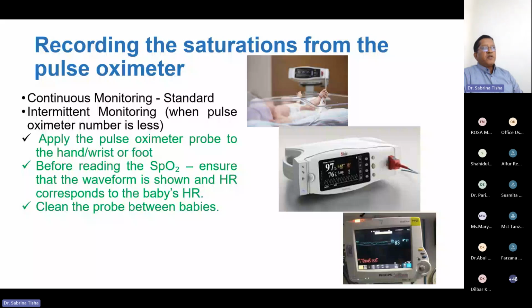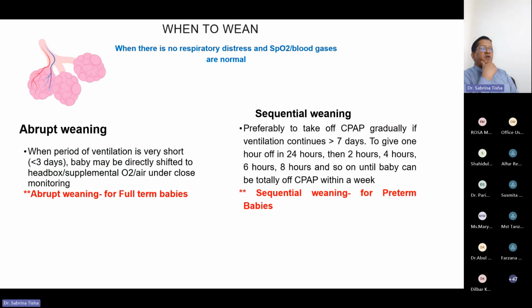And for pulse oximeter check, apply the pulse oximeter probe on the hand, wrist or foot, and before reading the SpO2, we need to ensure that the waveform is shown in the display, in the monitor, as well as check the heart rate manually to confirm that the heart rate showing in the monitor is equal to what I am checking manually. And clean the probe between babies. And when to wean? Readiness is determined when there is no respiratory distress and SpO2 and blood gases are normal. So two patterns of weaning. One is abrupt weaning.